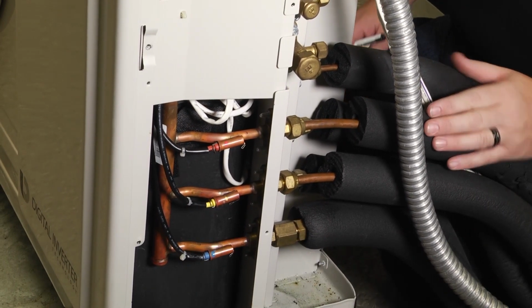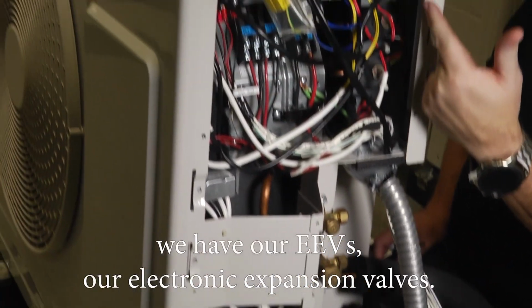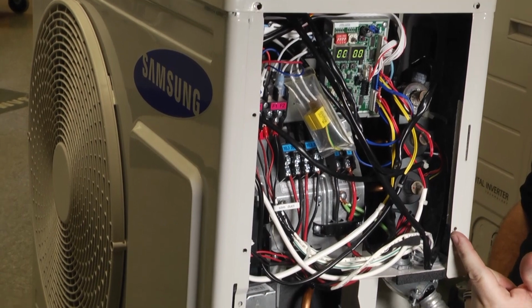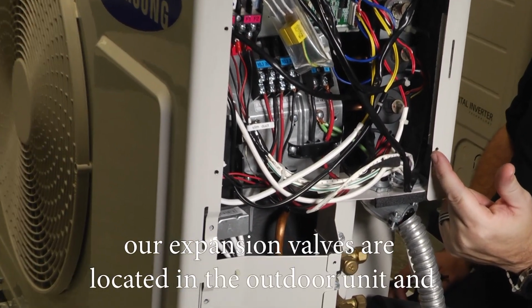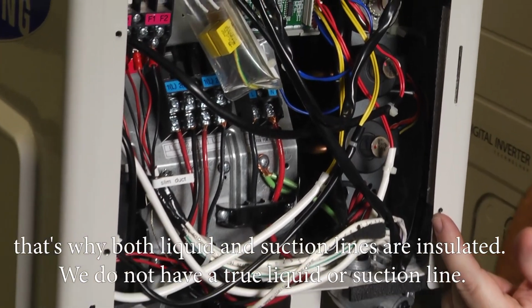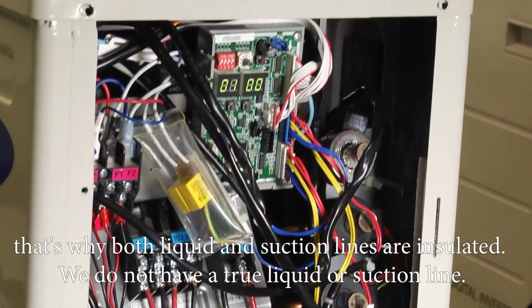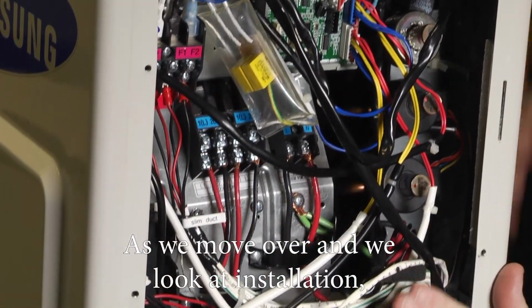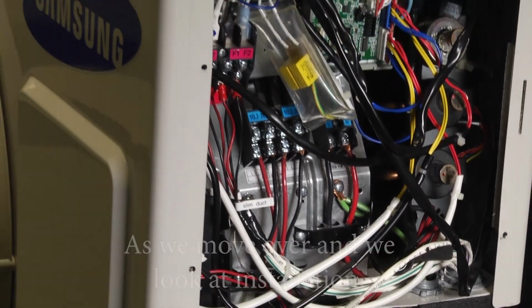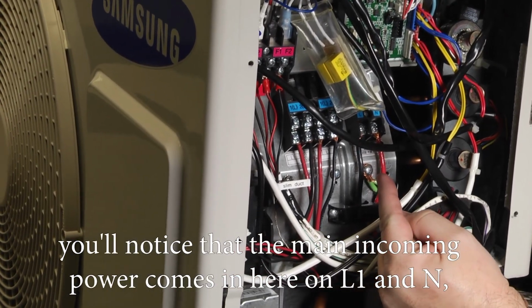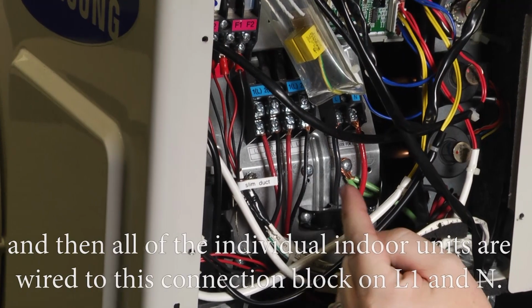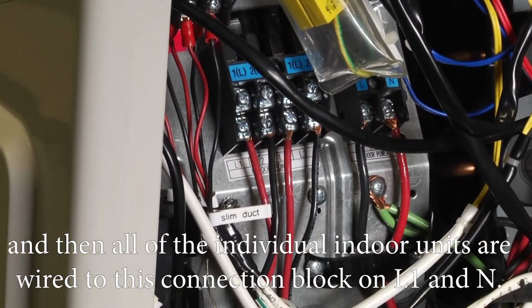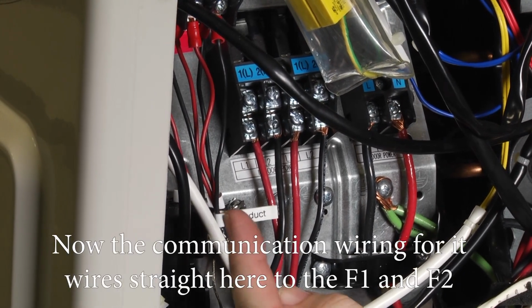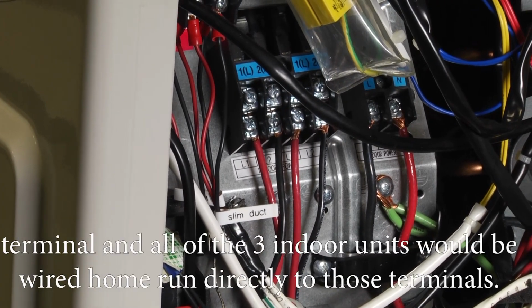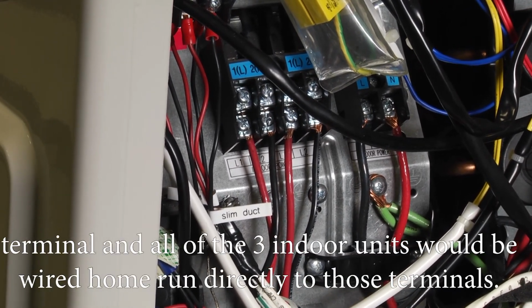Now you'll notice right here on the right hand side we have our EEVs, our electronic expansion valves. Just like our residential light commercial product, our expansion valves are located in the outdoor unit, and that's why both liquid and suction line are insulated, because we do not have a true liquid or suction line. As we move over and we look at installation, you notice that the main incoming power comes in here on L1 and N. And then all of the individual indoor units are wired to this connection block on L1 and N. Now the communication wiring for it wires straight here to the F1 and F2 terminal, and all of the 3 indoor units would be wired home run directly to those terminals.